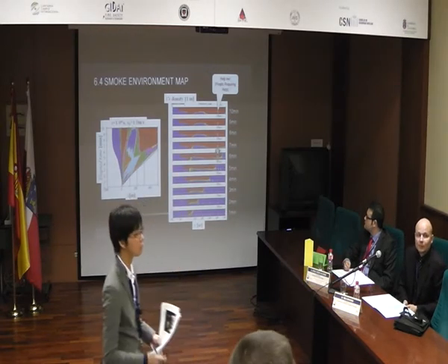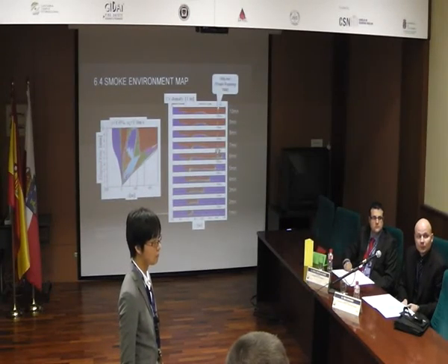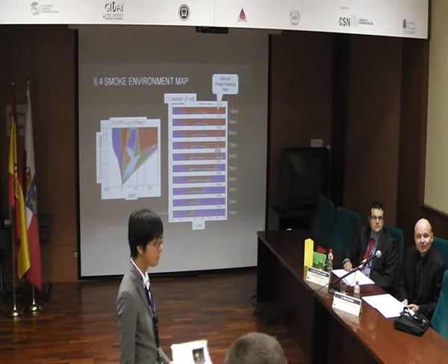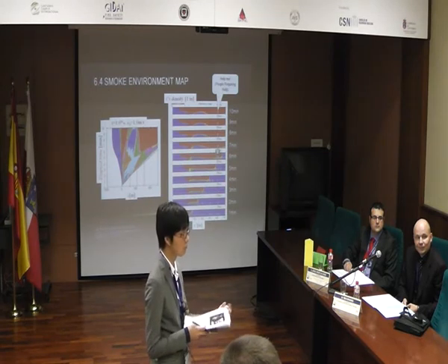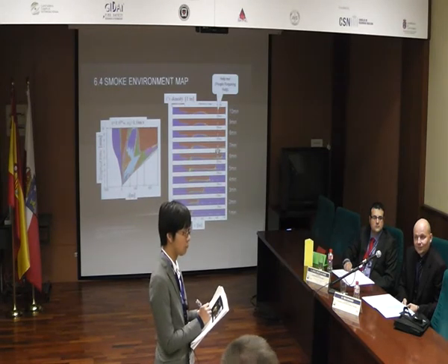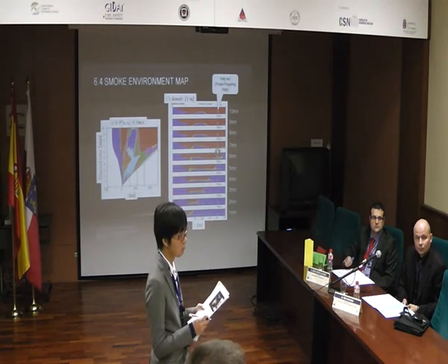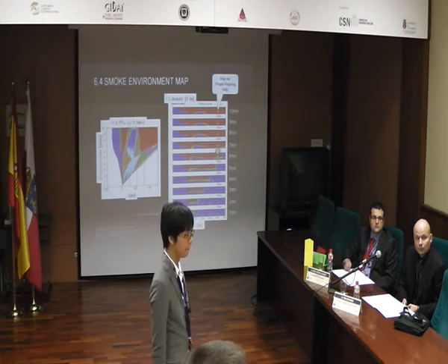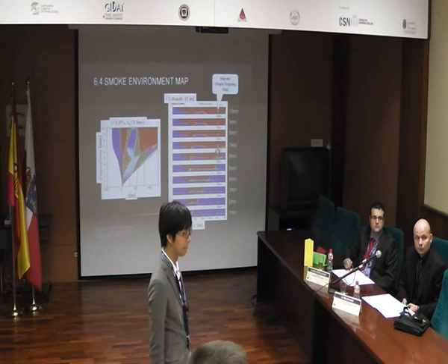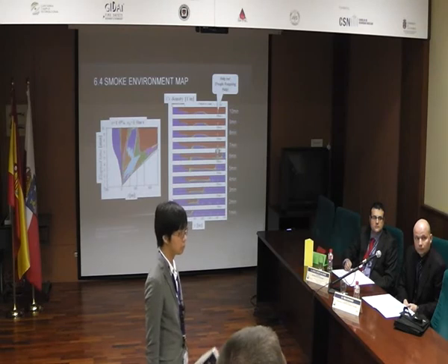Right. So this is a critical number because if walking speed is 1.2 meter per second, the people will go faster than the smoke. If the smoke goes at 2 meter per second, then many people will be trapped by the smoke, which is what we found at Mont Blanc, because the velocity of the smoke starts at 1 meter per second and then goes faster and faster. At the tunnel mouth, it's 5 meters per second. So it depends on your assumption on the flow in the tunnel.